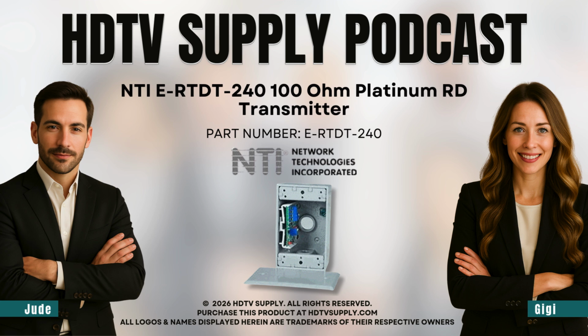That makes so much sense. Now, this specific model, the E-RTDT-240, is focused on a range from 30 up to 240 degrees Fahrenheit. Why would an engineer pick this one when there's another model, the E-RTDT-140, that goes way colder, down to -20? That's about specialization. It usually means you get better resolution. The 240 model is optimized for hotter environments. Think about steam lines, certain manufacturing processes, or just really hot equipment cabinets. So you're trading a wider range for more detail in the range you actually care about. Exactly. By narrowing that focus to 30 to 240 degrees, you often get slightly better signal fidelity right in that specific operational window.